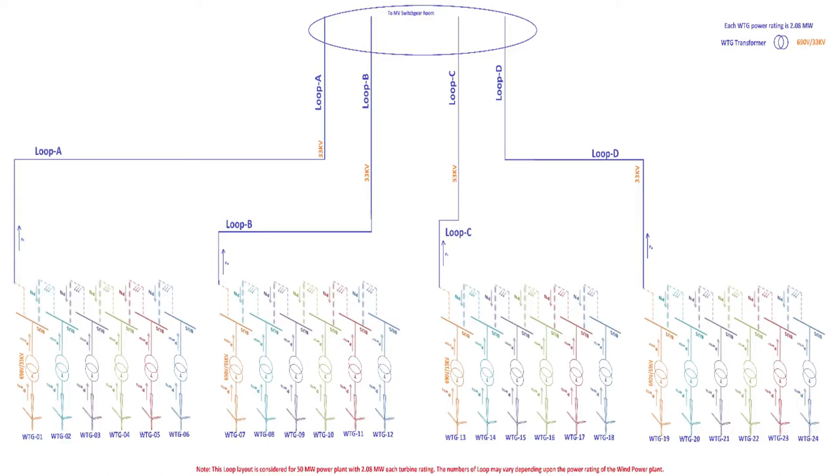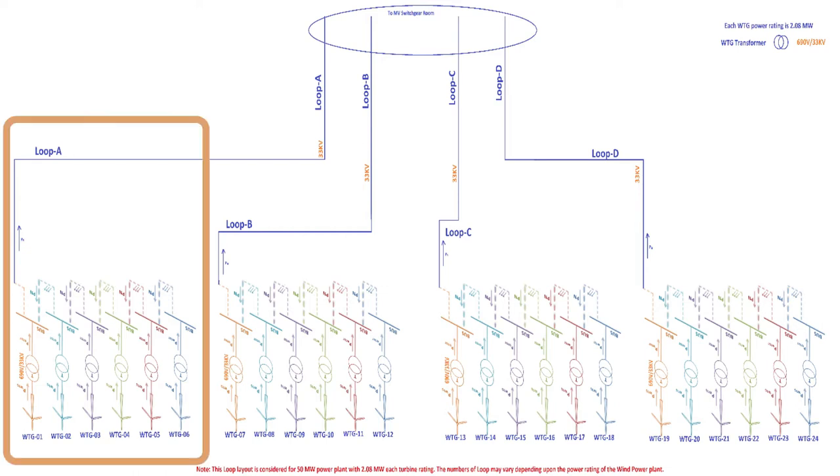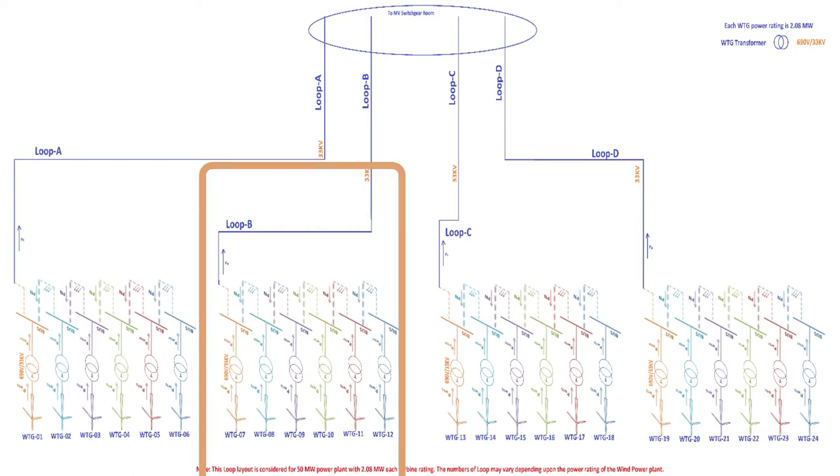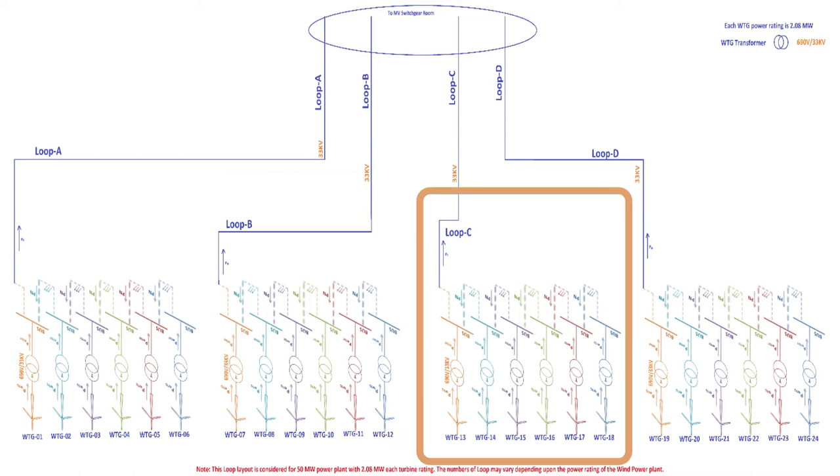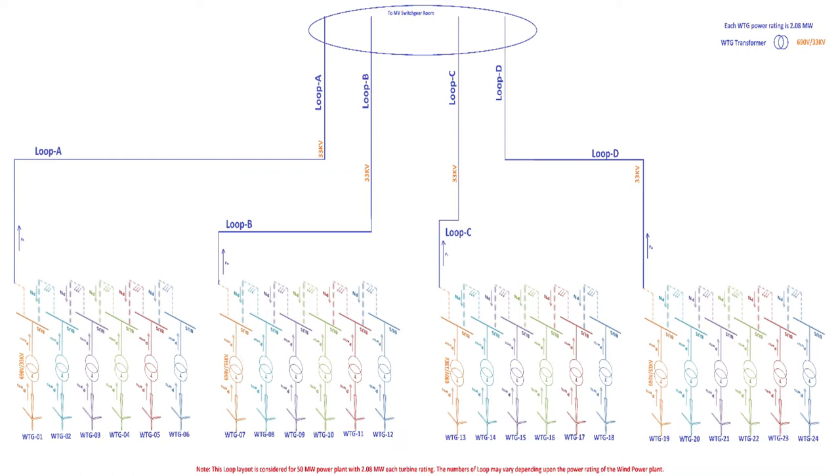For your understanding, this picture shows turbines' loop for a 50 MW wind power project having a power rating of 2.08 MW each wind turbine. 24 wind turbines will be required to achieve 50 MW capacity. These turbines are grouped in 4 loops: loop A, loop B, loop C, and loop D. Each loop consists of 6 turbines.